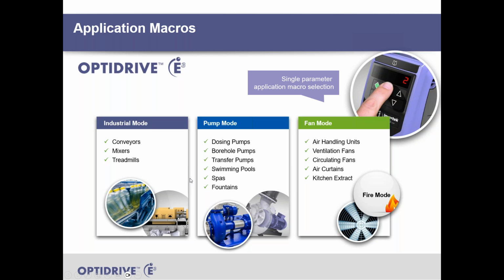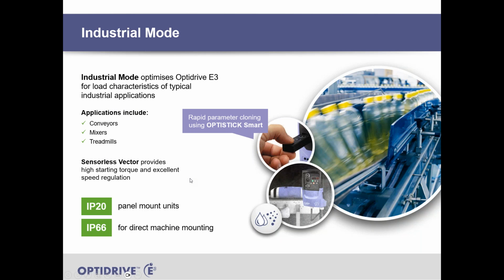So industrial mode, it's optimized for load characteristics of constant torque applications, so typical industrial type applications. We have an exceptionally good sensorless vector control algorithm in the drive, which gives us good high starting torque for starting loaded conveyors, for example, and excellent speed regulation if we have load changes on the application. And of course, the firmware is common for the IP20 or the IP66 units.